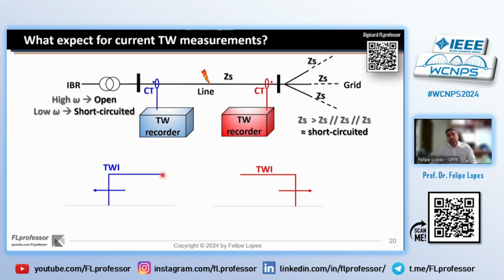In this case, the traveling waves will reach both line terminals, and reflections will appear. On the grid side, where usually there are other transmission lines emanating from the bus, it is expected that the wavefront will see the parallel association of the surge impedances of all of these lines. And this parallel association will be smaller than the surge impedance of the line from where the traveling wave is coming, in such a way that the measurement will be the sum of the incident wave and the reflection, which will be a positive reflection, and it will amplify the measurement here.